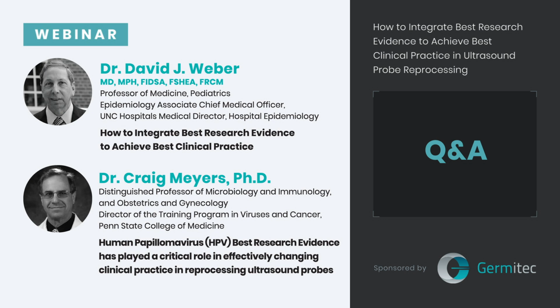Obviously, if you change your device and you go from a device that has a chamber size of, say, just as an example, 15 centimeters by 15 centimeters by 20 centimeters, and now you make a device that has 3 times the chamber size, or you change the configuration in the chamber, or you change the intensity of the UV bulbs or the gas concentration, then you need to revalidate the device. Generally, these devices, of course, are approved by the regulatory agencies in different countries, and you would follow the rules those regulatory agencies have for when you need to revalidate the device. But you're right, you couldn't assume that a device made for one application, if it changes in important parameters, would be safe.